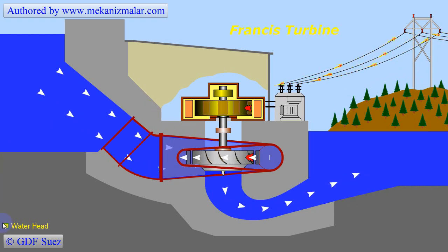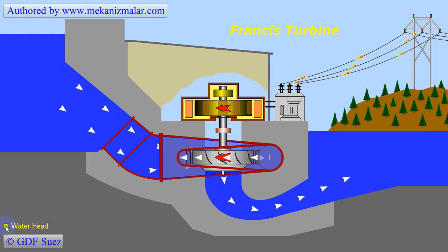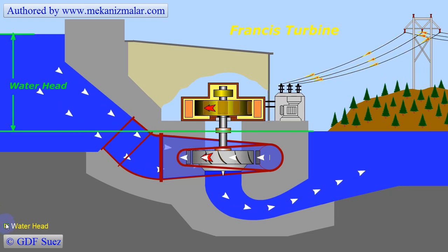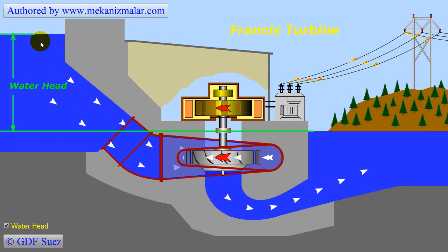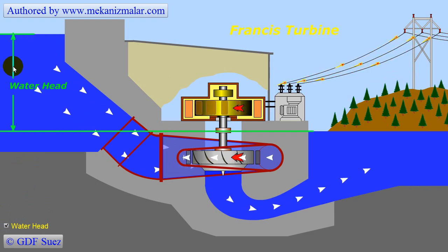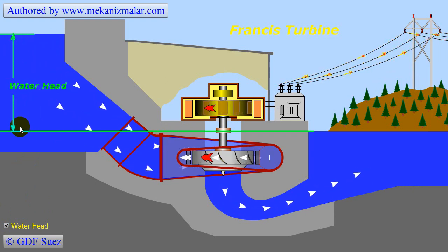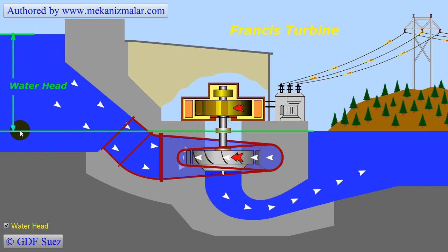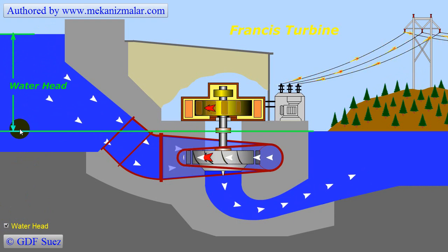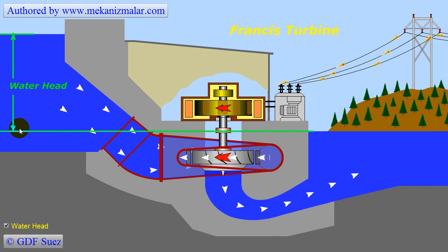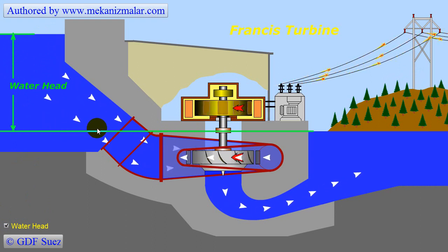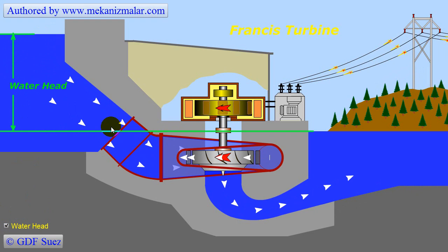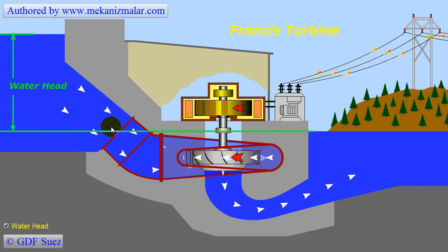There are three major types of water turbines. The Pelton turbine requires large water head and low flow rate, while the Kaplan turbine requires low water head but large flow rate. The Pelton turbines are usually built in mountainous regions, while the Kaplan turbines are located in lowlands. These restrictions make these two kinds of turbines less common than the Francis turbine.